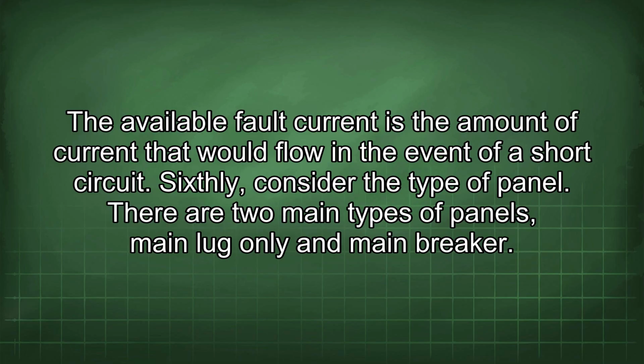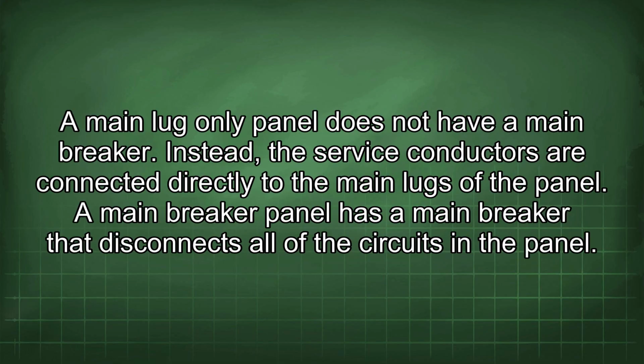Sixthly, consider the type of panel. There are two main types of panels, main lug only and main breaker. A main lug only panel does not have a main breaker. Instead, the service conductors are connected directly to the main lugs of the panel. A main breaker panel has a main breaker that disconnects all of the circuits in the panel.